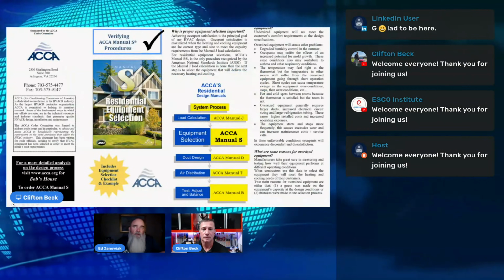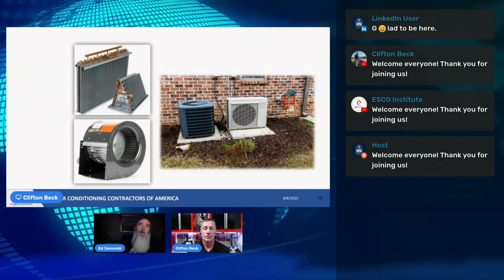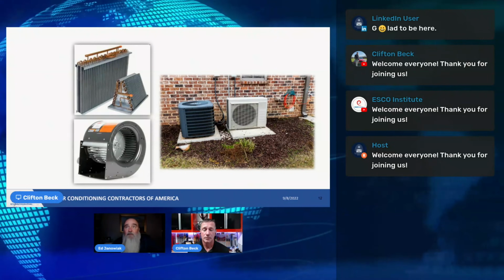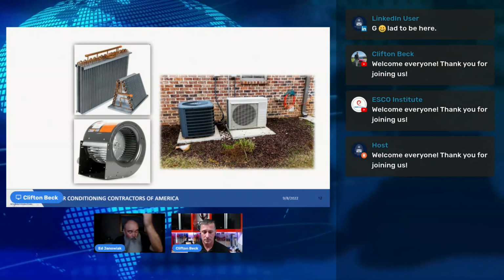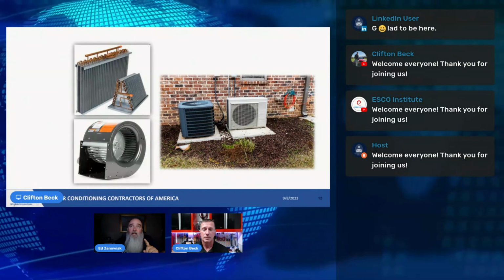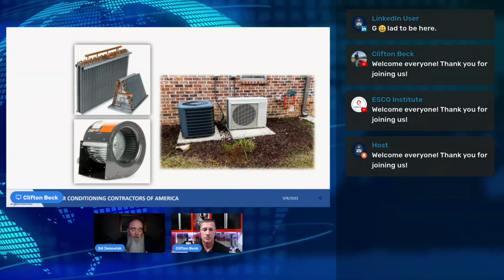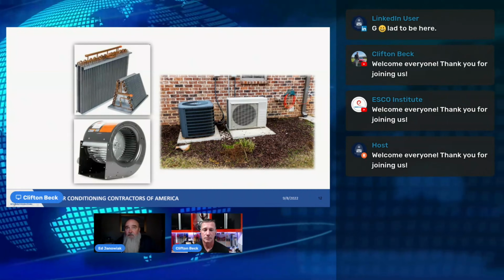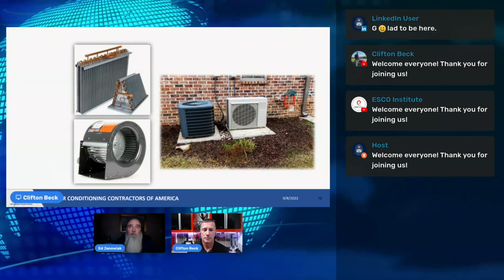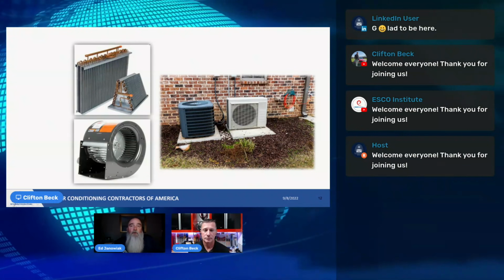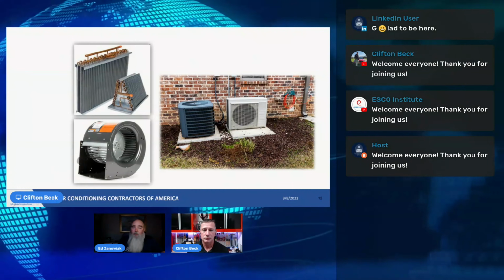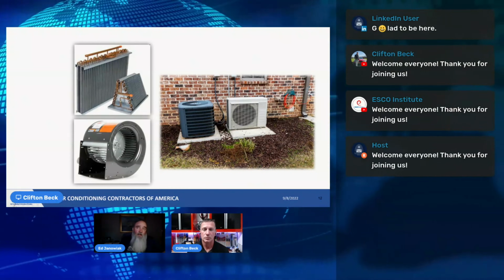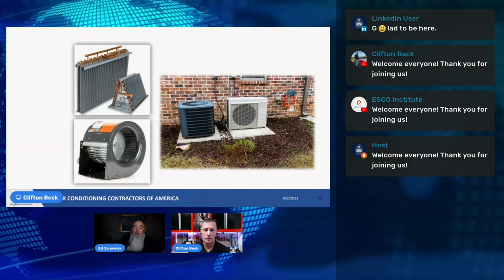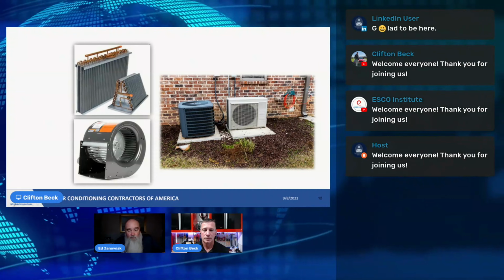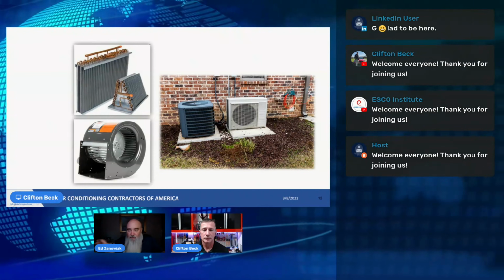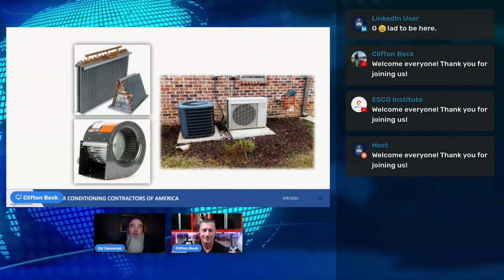So when we talk about Manual J, the next part is Manual S. Manual S gives us guidance for selecting an indoor coil, blower size, and equipment to match it to. One thing people tend to forget - I use that picture of the traditional outdoor unit versus what looks like a traditional mini split - mini splits rely on the same set of rules as a traditional unitary split system.